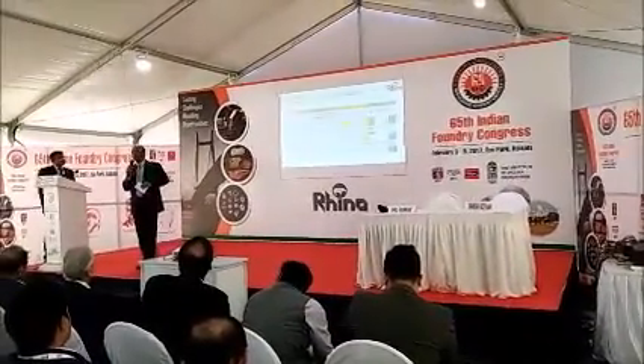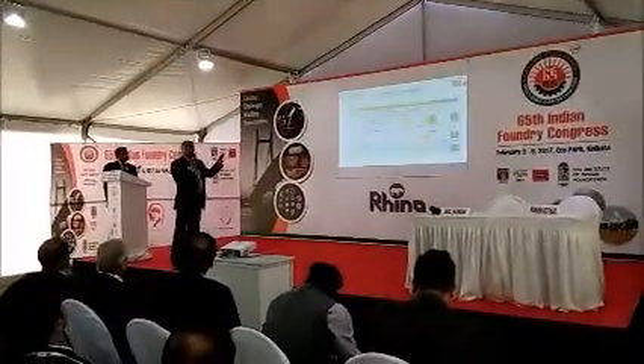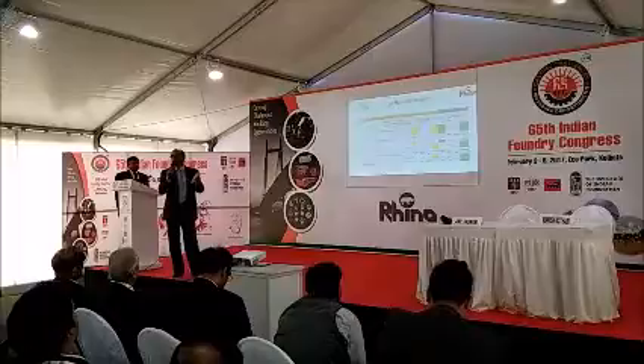For example, then I was telling about KVA. Whatever KVA you have, contract demand and billing KVA, 750 KVA, but looking at the graph, rarely does it go to 750 and the balance of the time it works at 500 KVA. So by improving power factor also you can reduce KVA.